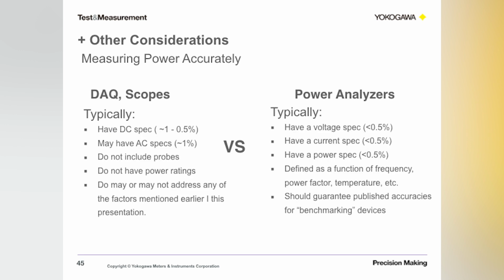Both of them have their pros and cons. A typical DAQ device will only specify DC accuracy specifications. They may or may not specify any AC specifications. They're also usually voltage inputs and need external sensors for current input, even in the low current ranges, whereas a power analyzer would directly accept those current signals. The accuracies don't include probes, so you have to calculate those accuracies out and include them separately with the overall calculation, and they may not address any of the uncertainty factors that I described today in this presentation.